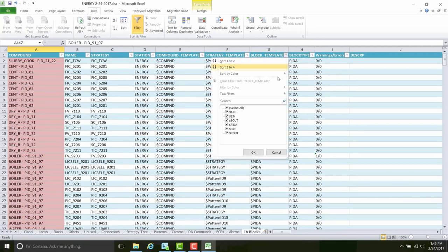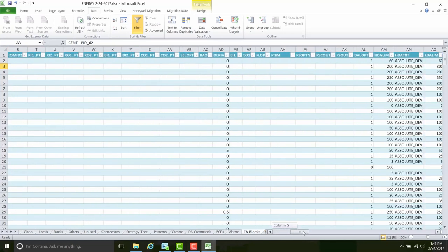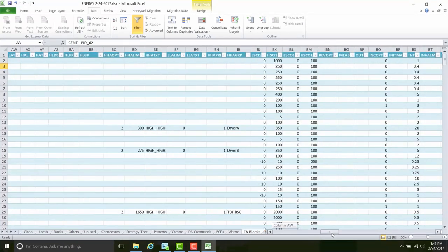Next, all the critical regulatory control blocks are converted automatically. Converted blocks are also color-coded for analysis and review. When the value doesn't fit with our EcoStruxure Foxboro DCS, the cell goes red. This can be due to configuration mistakes or syntax errors within the existing system that have gone undiagnosed. For PID controllers, everything is converted, including configuration parameters and tuning parameters.